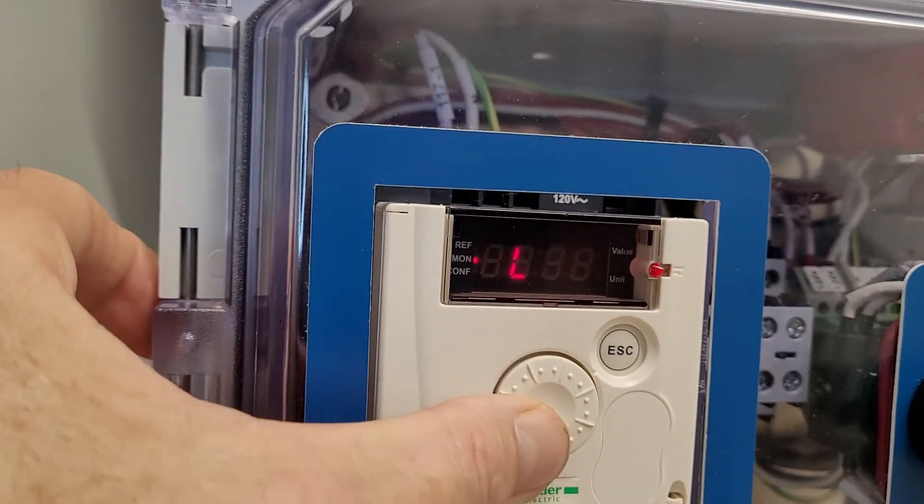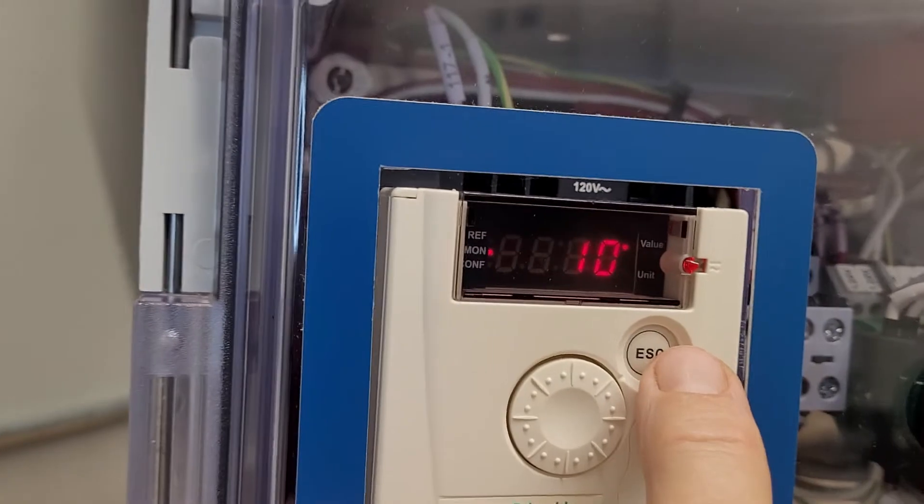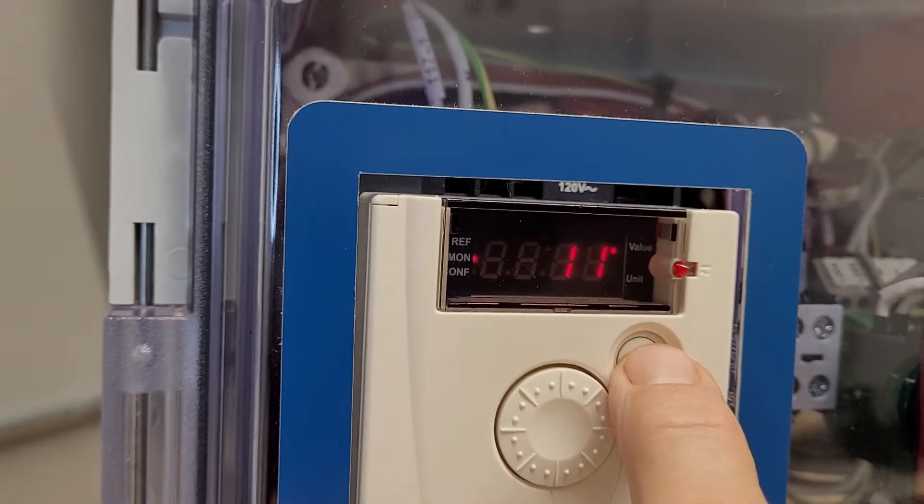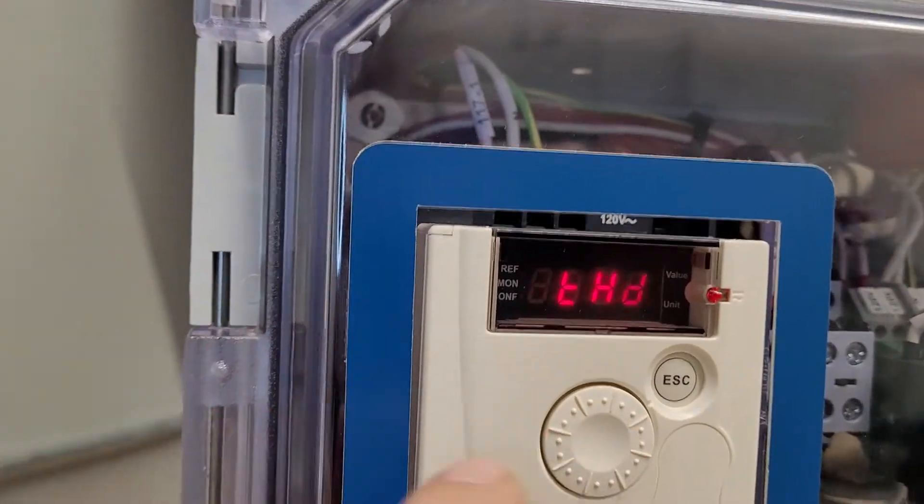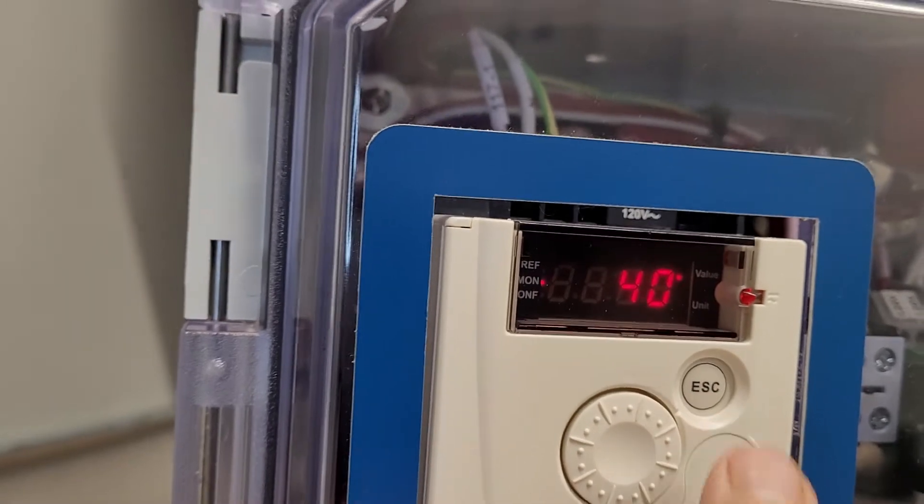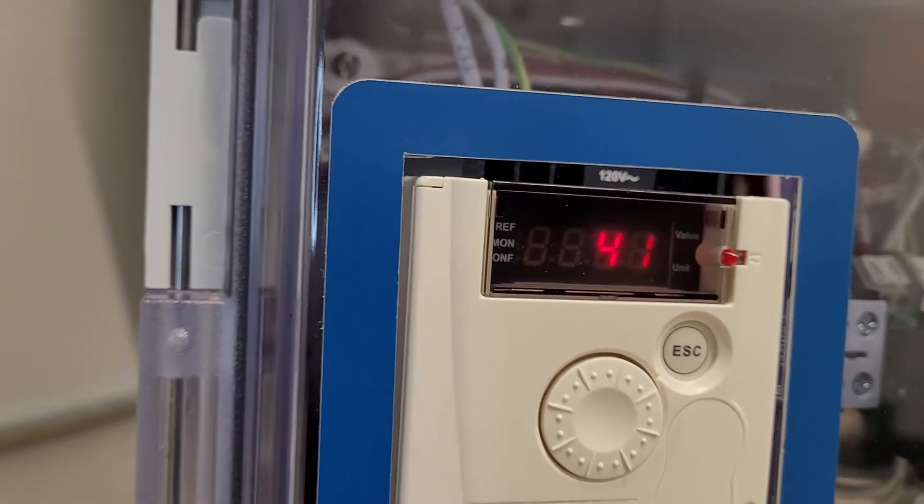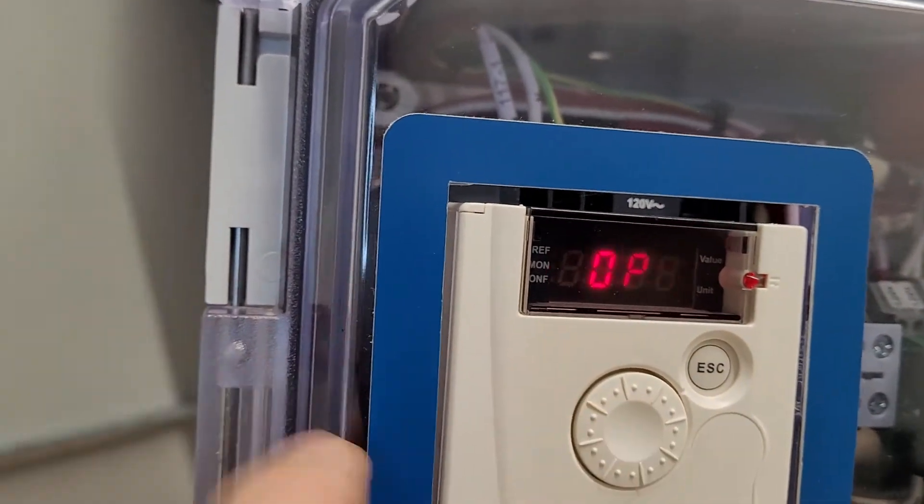I just exited out by mistake there. Now we are in THR. That is the thermal state of the motor. It is only at 10% so it is doing really well. You will see it creep up. And then the next one down is the thermal state of the drive. It is operating at about 40% of its maximum temperature. I will hit ESC and go down to the next one.